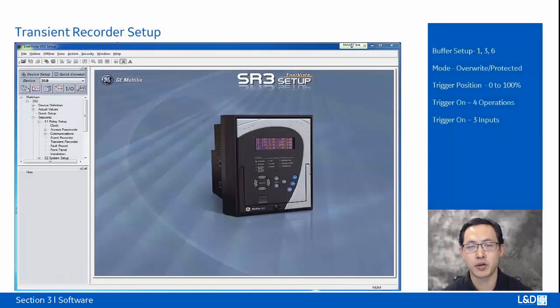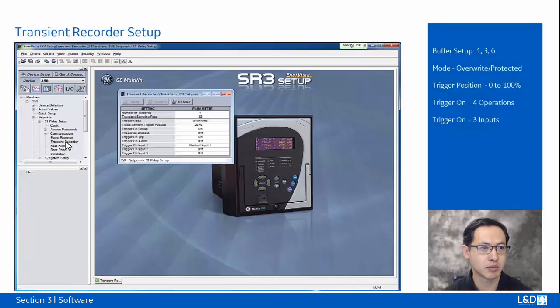Transient recorder is a very useful troubleshooting tool. In order to get a perfect COMTRADE file, we need to properly set up the transient recorder. So to get into the transient recorder, we go to Set Points, Relay Setup, and Transient Recorder, double click, and there are lots of settings we can do with the number of records. We can pick 1, 3, or 6. So when you choose fewer records, you can record a much longer waveform.